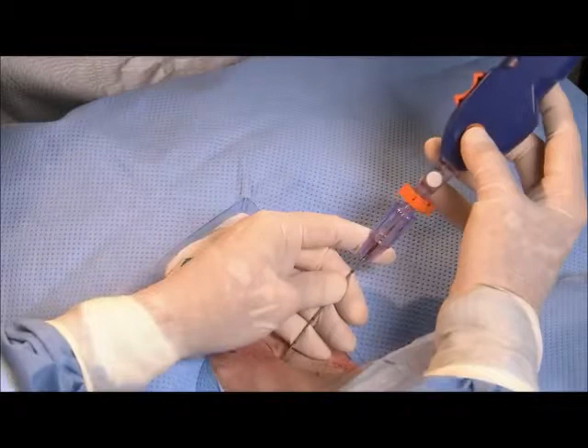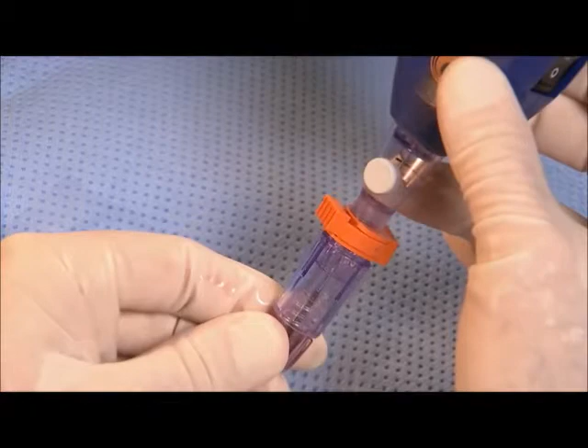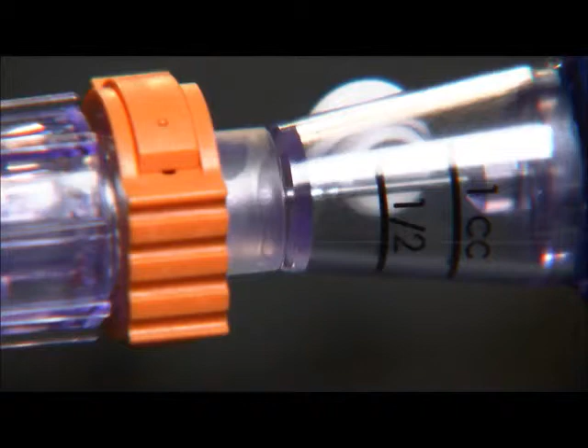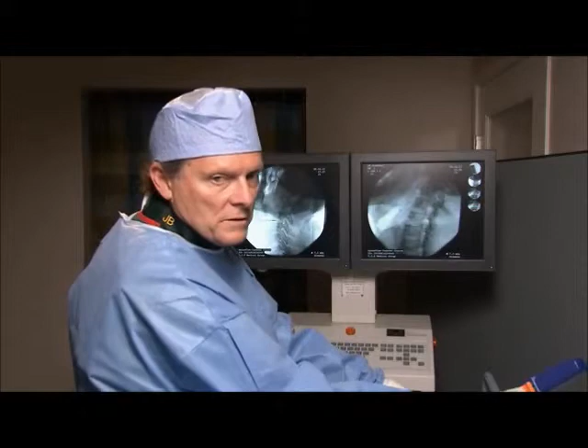So with the motor running, with the tip deployed, I can advance and retract back and forth as many times as I need, looking for material being pulled back into the collection chamber. That collection chamber is marked with a 1/2 and 1 cc mark. I try to get somewhere between there. When I run the motor, it could take anywhere from 15 seconds to a couple of minutes to get enough nuclear material.